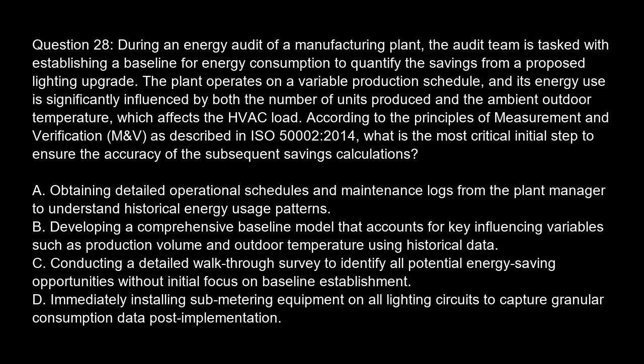The correct answer is B: developing a comprehensive baseline model that accounts for key influencing variables such as production volume and outdoor temperature using historical data. Explanation: the core principle of measurement and verification (M&V), as outlined in ISO 50002:2014, is to establish a baseline for energy consumption and then quantify the energy savings achieved by implementing energy efficiency measures.